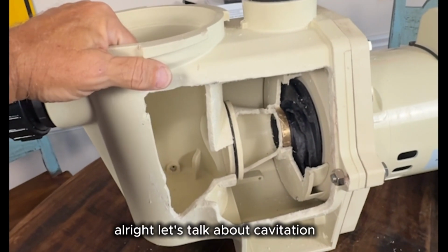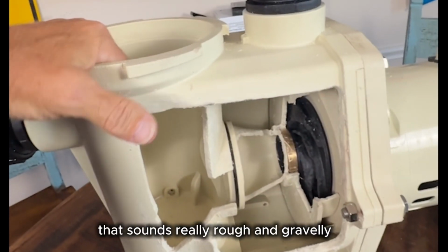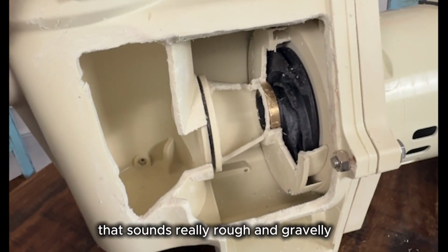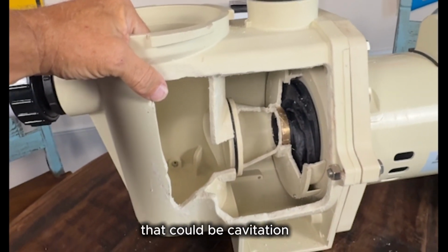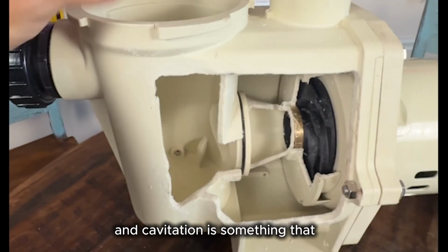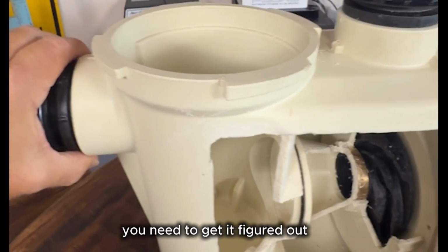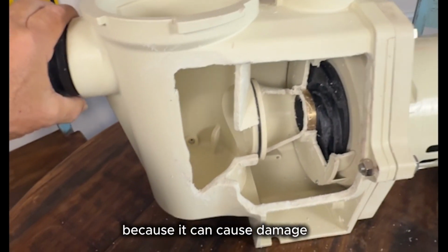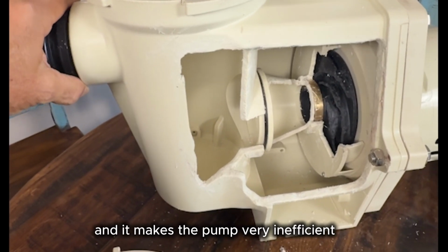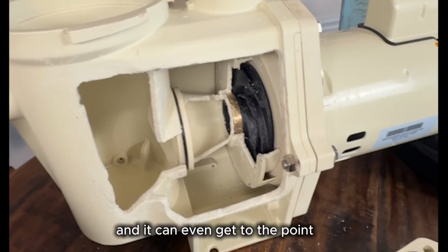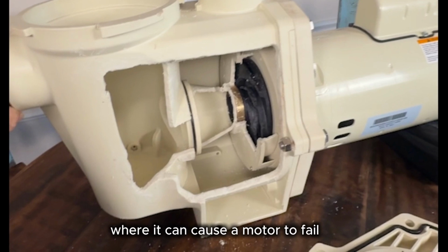All right, let's talk about cavitation. If you ever hear a pump that sounds really rough and gravelly, that could be cavitation. And cavitation is something that, if it's going on with your pump, you need to get it figured out, because it can cause damage and it makes the pump very inefficient, and it can even get to the point where it can cause a motor to fail.